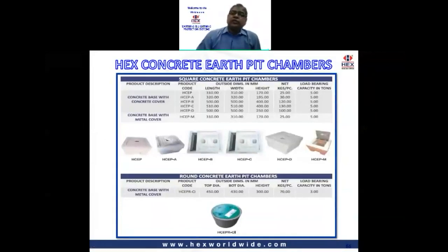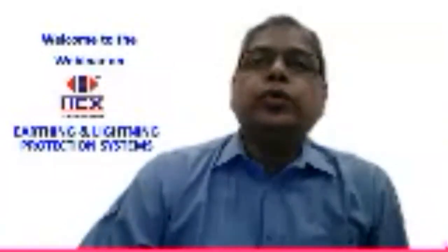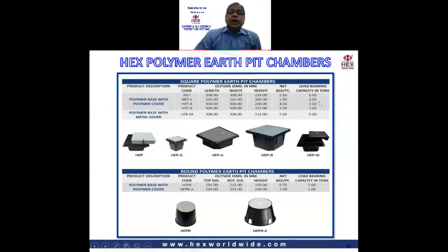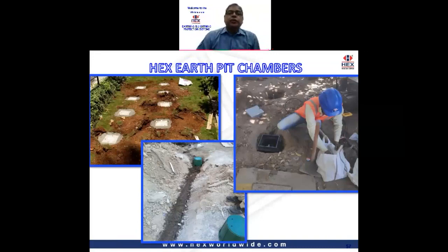Now, by using these chambers, you can save crucial time in building chambers using bricks and cement and concrete. Now, we have ready to use polymer chambers, four in square shape and two in round shape. The smaller sizes of the square chambers have been tested successfully for 5 tons and the bigger sizes for 3 tons. These are manufactured from high grade polypropylene for high strength. They are also stabilized against UV degradation by sunlight, and they are also non-brittle. As they are lightweight, they can be transported very easily. They also have been tested successfully as per IEC 62561-7.